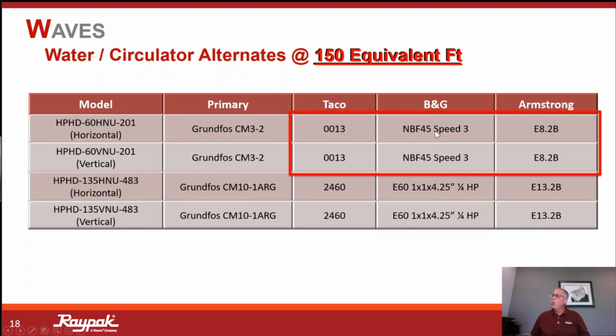Then we went to an NBF 45, but now instead of speed 2, now we're on speed 3. And then finally, the Armstrong, previously it was an E7, and now we're at an E8. Okay, so again, modest differences in our pump selection to get us that narrow temperature rise of between 5 and 8 degrees that we're looking for in these systems.